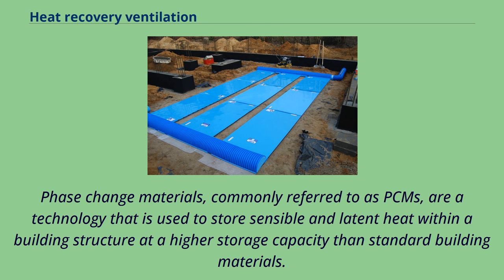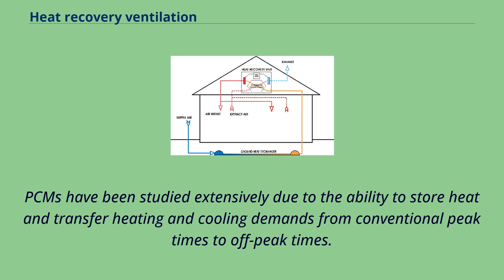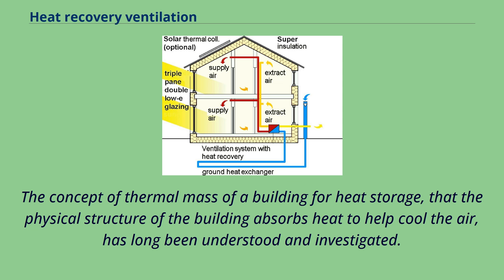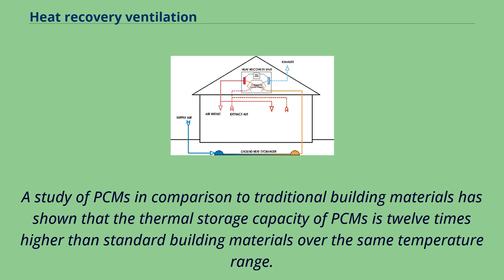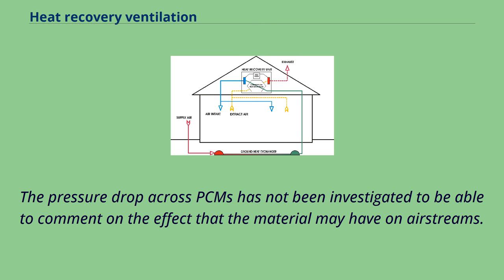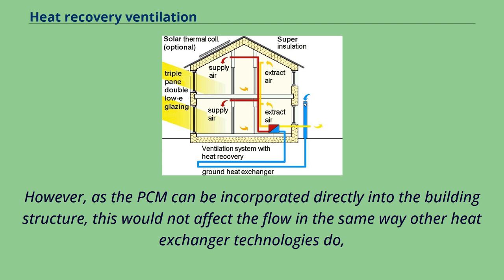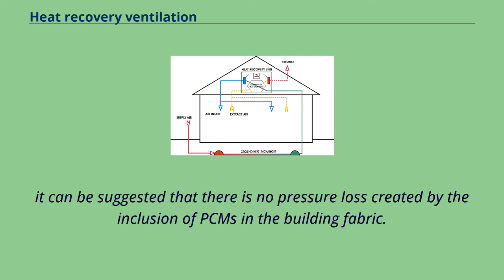Phase change materials, commonly referred to as PCMs, are a technology used to store sensible and latent heat within a building structure at a higher storage capacity than standard building materials. PCMs have been studied extensively for their ability to shift heating and cooling demands from peak to off-peak times. A study comparing PCMs to traditional building materials showed that thermal storage capacity of PCMs is 12 times higher than standard building materials over the same temperature range. As PCMs can be incorporated directly into the building structure, it is suggested there is no pressure loss created by their inclusion in the building fabric.